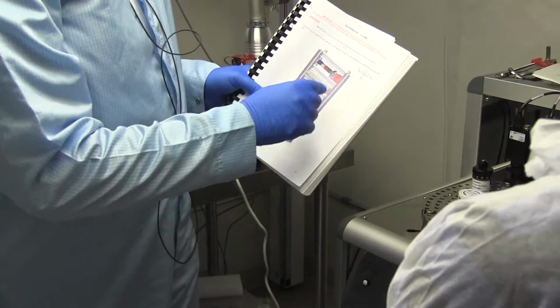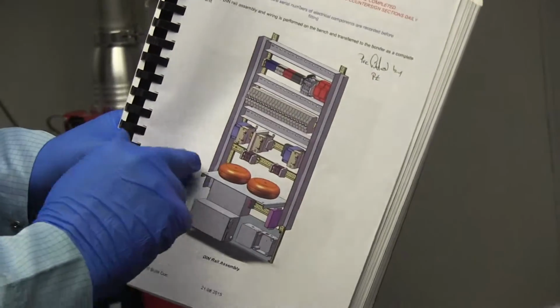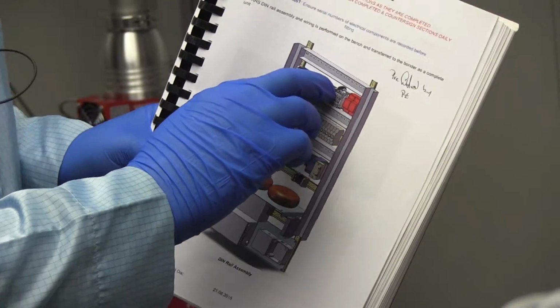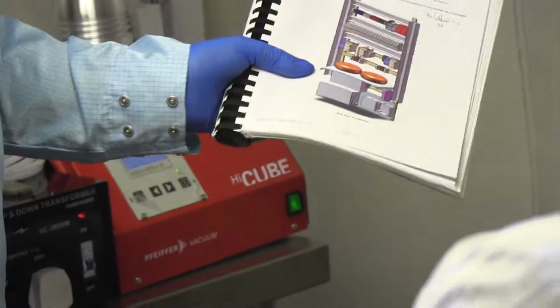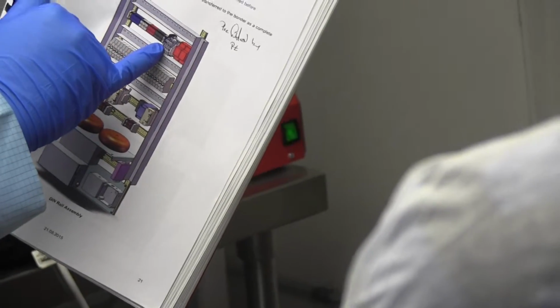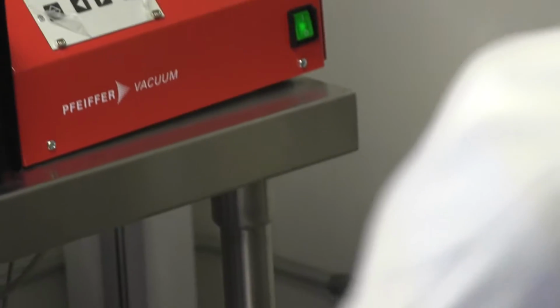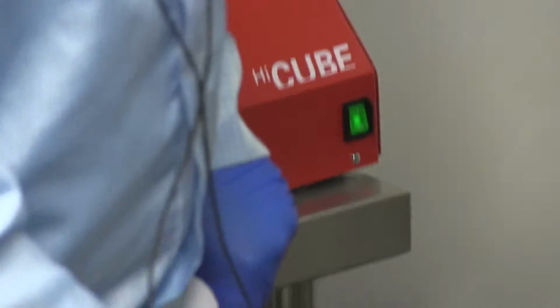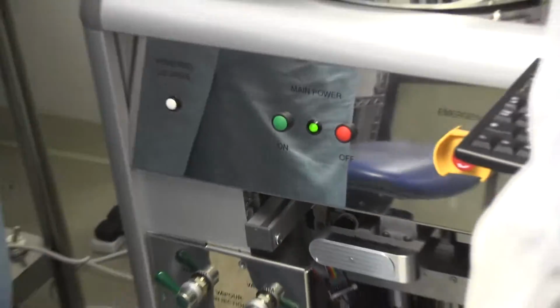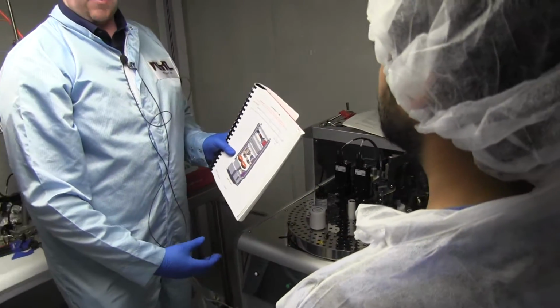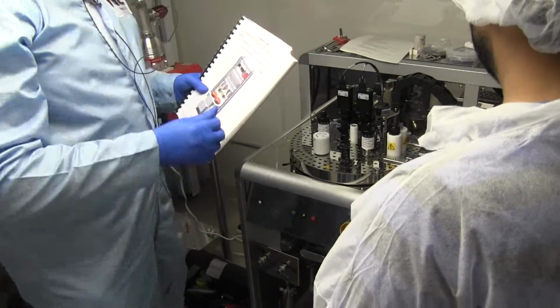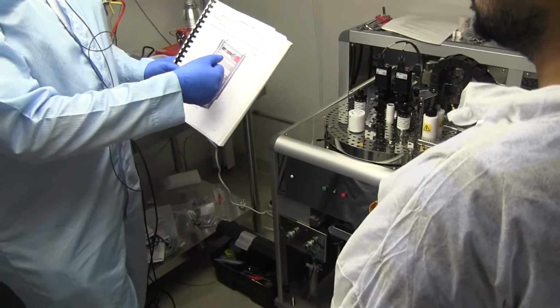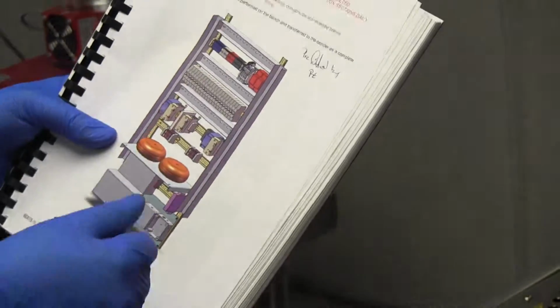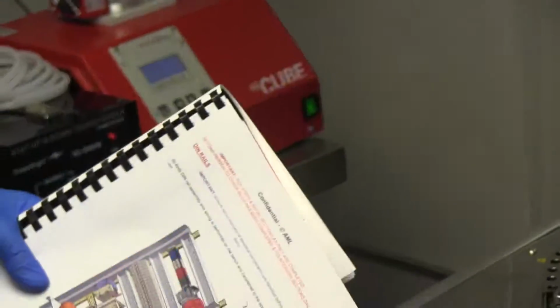Black and red is for 24 volts, so this power supply feeds those black and red, and then they in turn feed everything else that requires 24 volts. And then lastly there's a mains contactor, so when you first plug the machine in, there'll be 24 volts applied to these switches. Push the on switch, the 24 volts will then be used to latch this contactor, which then brings in the mains voltage to everything else. And two surge protectors. So in the event of, say, a lightning strike or any voltage surge, these will cut in to protect the rest of the system.